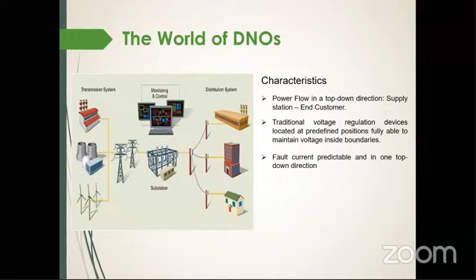Similarly, fault currents were highly predictable and also in a top-down direction from the supply substation to the fault location. Protection equipment was located at predefined critical locations and preset to react to these highly predictable, unidirectional fault currents. It was almost a set-and-forget method, where protection equipment would be set and coordinated once per year or once per season, and fully able to protect the whole grid without almost any interaction by DNOs. So DNOs were able to manage the grid using simple paper-driven processes, with almost no need for interactive action in real time.